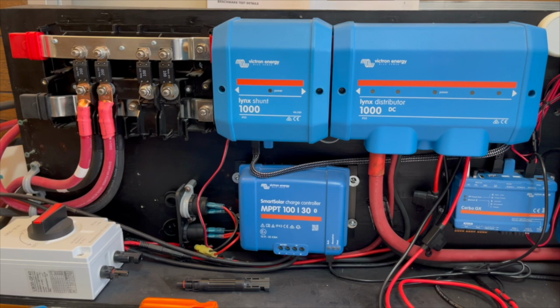That's also the unit I use to set my AC off-grid limits. If I'm connected to 15 amps, or to a 15 amp generator, I let the unit know I only have 15 amps. You can set this up in increments from 1 to 30 amps, and when it goes over 15 amps, the system will take the rest from the battery bank.